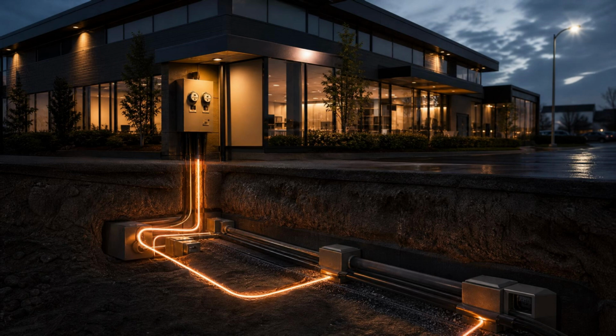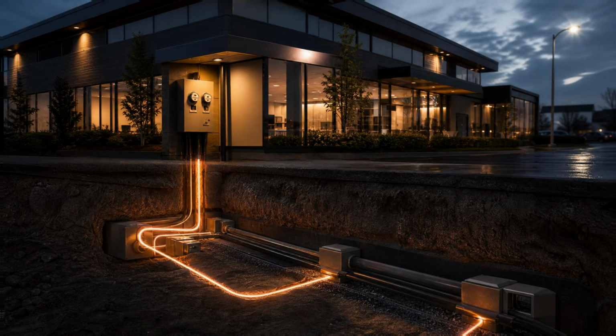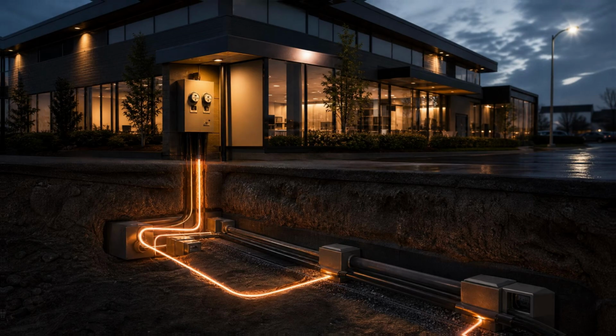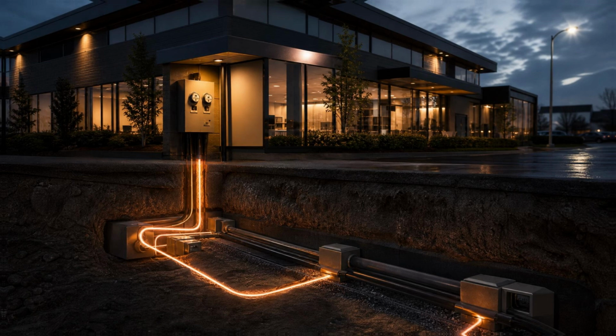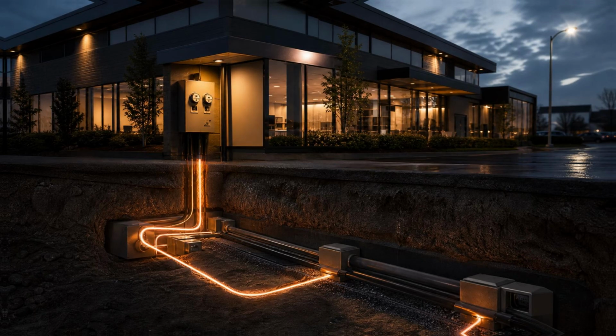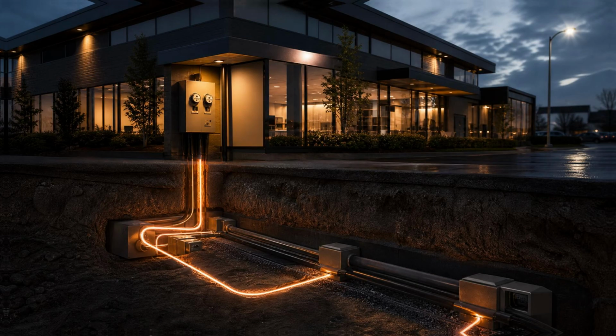any person to react. If an emergency power system responded to every flicker, if it treated every brief sag in voltage as a true emergency, it would be activating and resetting constantly. The equipment would wear prematurely. The power transitions would be more disruptive than the brief disturbances they were trying to address. And so there is, built into the monitoring logic, a kind of patience. A brief window of time, sometimes just a second or two, sometimes a few seconds more, depending on the application, during which the system observes the disturbance and waits. Is this still happening? Is this getting worse? Or has the utility already recovered on its own?